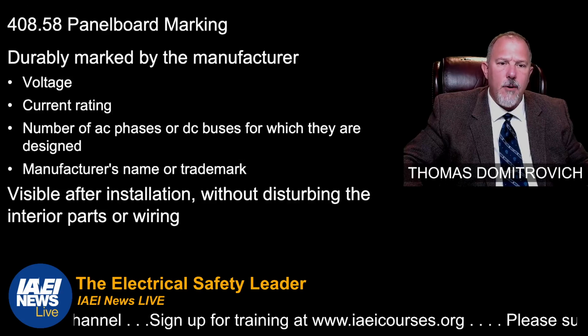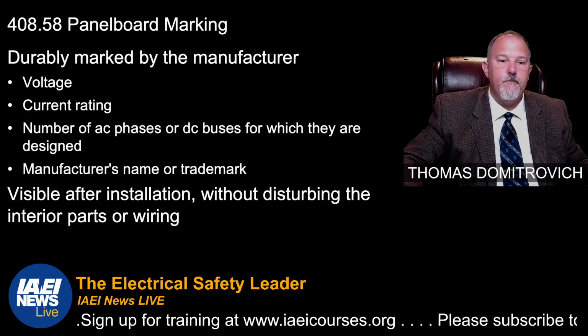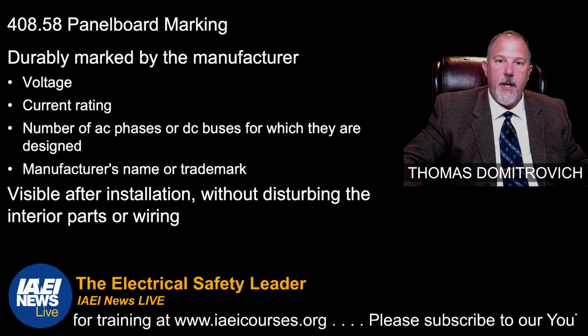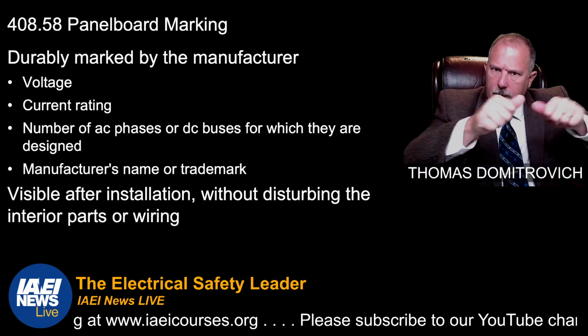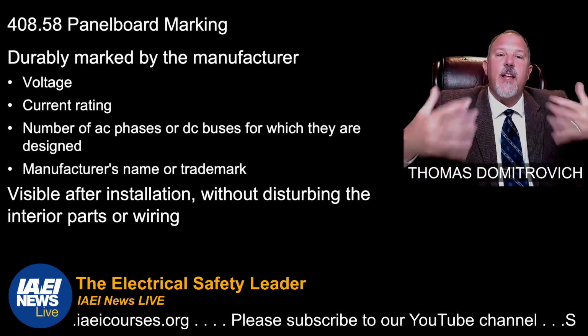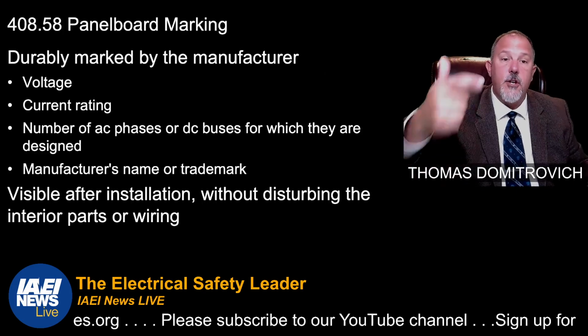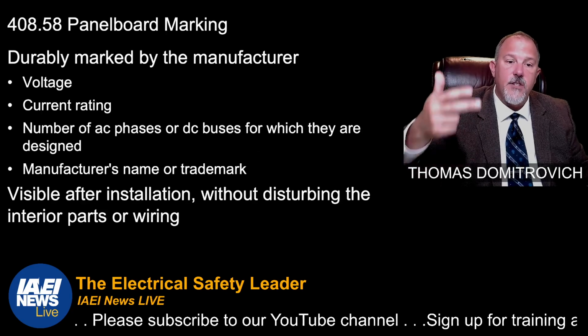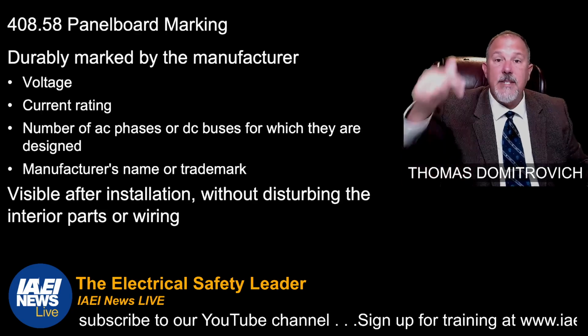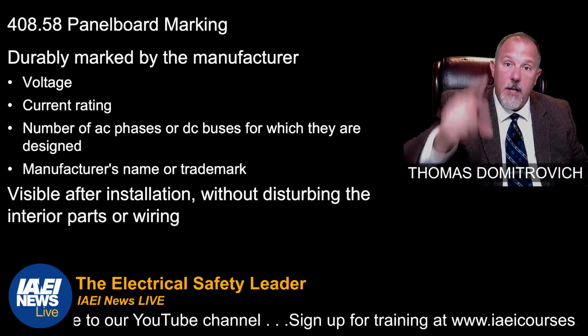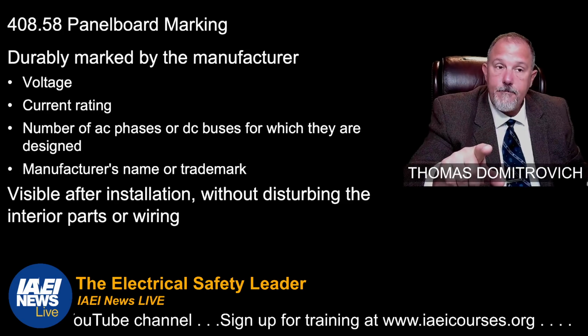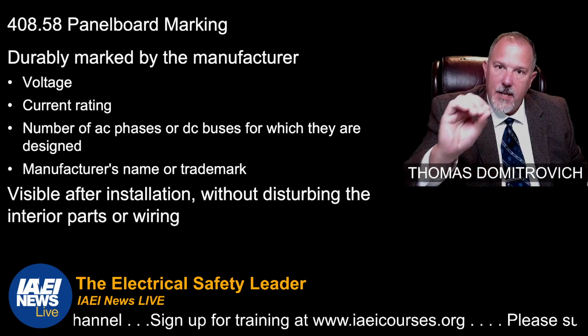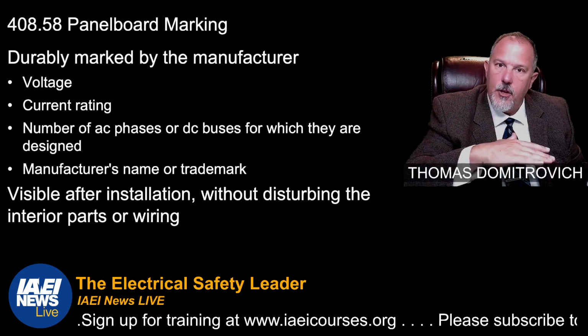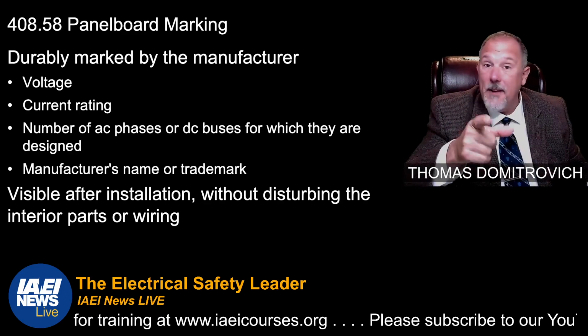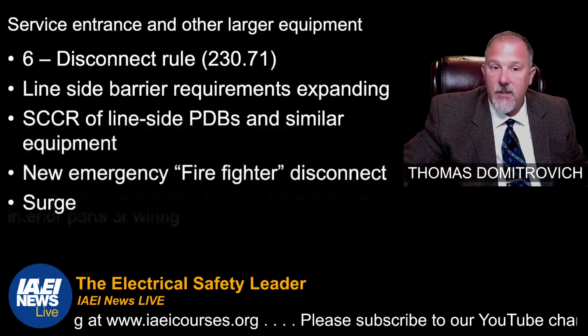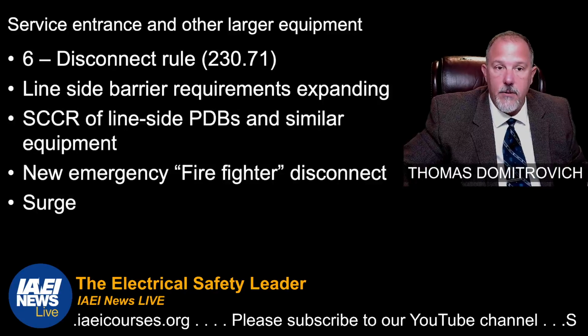Panel board has to be marked durably. That doesn't mean that you just have to put a little extra oomph. It has to withstand the environment. You have to have the voltage, the current, the number of AC phases, and the manufacturer's name or trademark. Take a look at the link down below to the UL marking guide, because it'll tell you all of the different marks that you may see on a panel board and why they're there. That's a good resource. I love that resource.